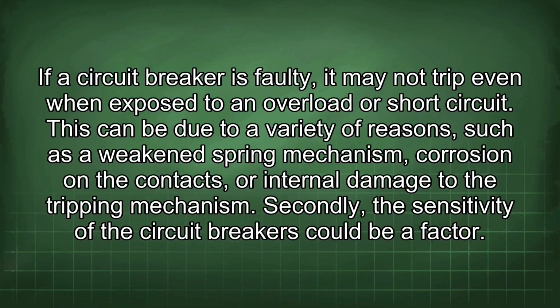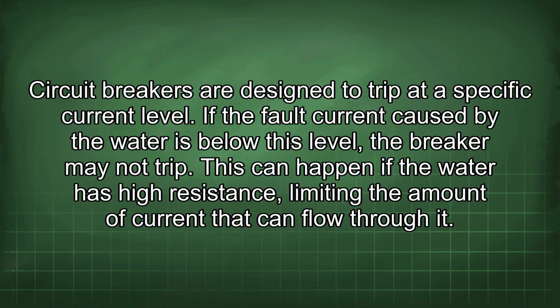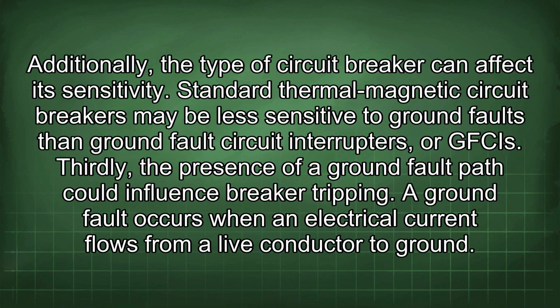Secondly, the sensitivity of the circuit breakers could be a factor. Circuit breakers are designed to trip at a specific current level. If the fault current caused by the water is below this level, the breaker may not trip. This can happen if the water has high resistance, limiting the amount of current that can flow through it. Additionally, the type of circuit breaker can affect its sensitivity. Standard thermomagnetic circuit breakers may be less sensitive to ground faults than ground fault circuit interrupters, or GFCIs.